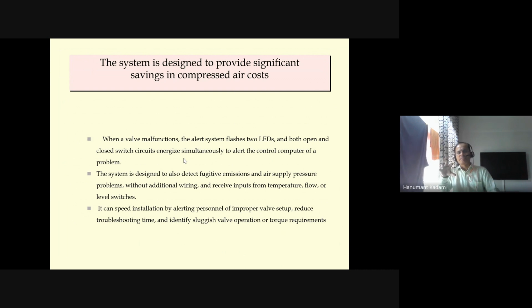So the built-in detection covers emissions, because the valve is used for some hazardous gases, and if it is leaking, that leakage is immediately detected, and you will get an alarm in the field as well as in the control room or with the fire team. It can also receive input from temperature, flow, or level switches.